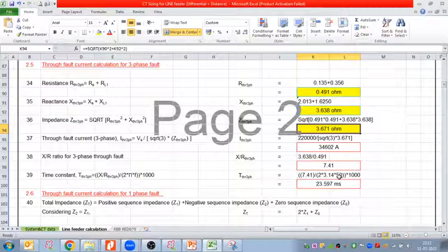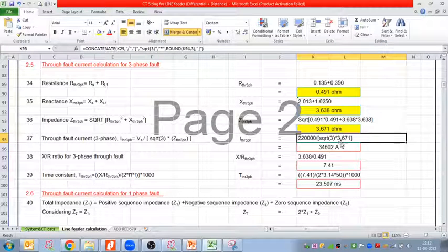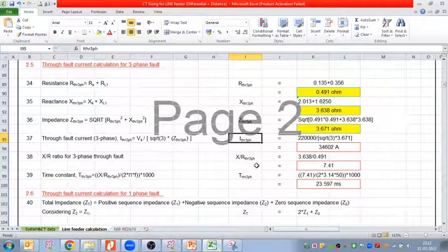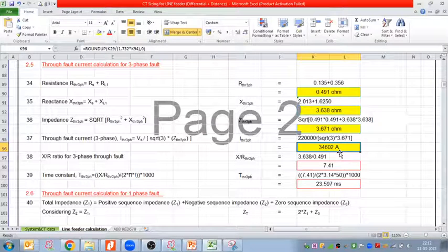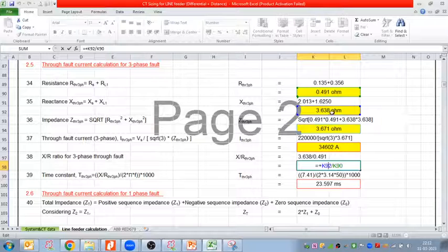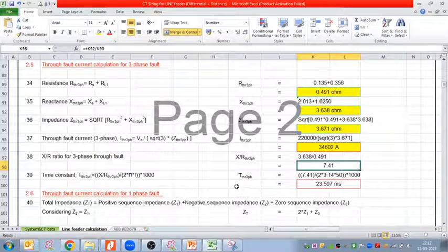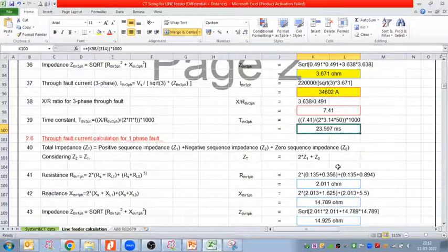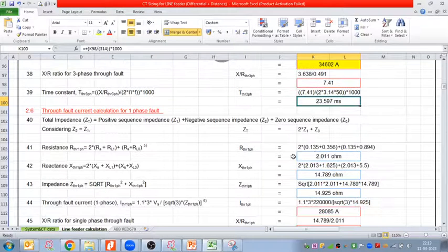So once we know Z, we can find I. So I is equal to V divided by root 3 into Z. We divide by square root 3 into Z, 3.67 ohm, which gives the three phase fault current of 34.602 kiloampere, which is calculated here. Okay, X by R of the three phase fault. If we wanted to calculate X by R till the point of fault, we can also calculate that, because we know the R and we know the X. That would be 3.638 by 0.491, which comes to 7.41. If we wanted to calculate the time constant, that also we can calculate, right? But this is not required in the relay formula, but if we want, we can find it out also.